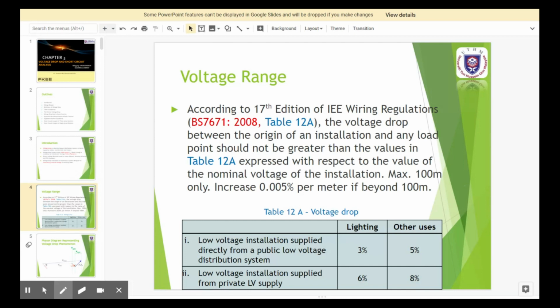That is allowed. So for example, if we look at the voltage drop table, for a low voltage installation supplied directly from a public low voltage distribution system, lighting is about 3%. The voltage drop allowed is 3%. Other uses is 5%. For example, if you have the distribution substation or DB, you have connected wiring to your house DB.